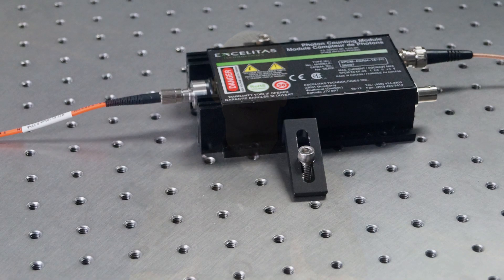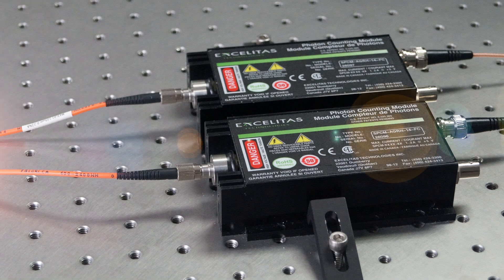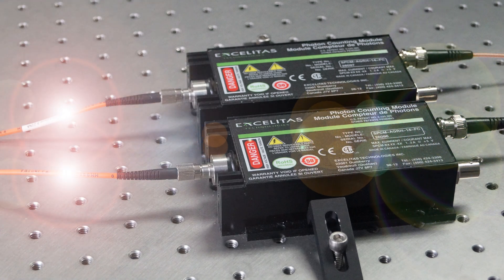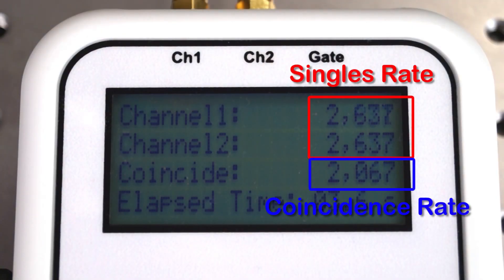This type of measurement is called a singles count because it reflects how many single photons the detector measured. For many experiments though what we're really interested in is coincidence rates. To measure coincidence rates, two detectors are used to measure photons coming from an optical experiment. Whenever a photon is measured in the first detector while simultaneously a photon is measured in the second detector, that's what we call a coincidence event. If these two detectors are plugged into the CC1, the unit will record both the singles rate for each detector and the coincidence rate between them. So in a nutshell, the CC1 measures the singles and the coincidence rates for two detectors.